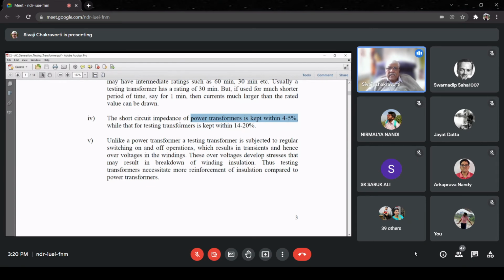But on the other hand, for testing transformers, we need to protect the transformer. Why? Because when I'm testing an equipment, I'm not sure whether it will be able to withstand the voltage or not. That's why it has come for testing. Some equipment will pass, some equipment will fail. But if an equipment fails, then it's a short circuit. So the short circuit current should not be high. We should keep it at a much lower value. That's why for testing transformers, this short circuit impedance is of the order of 20%.